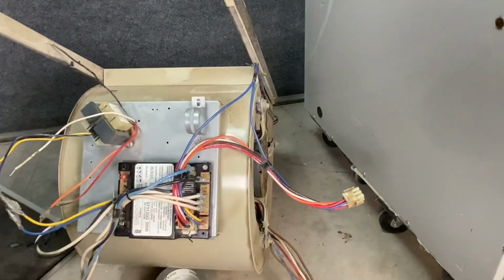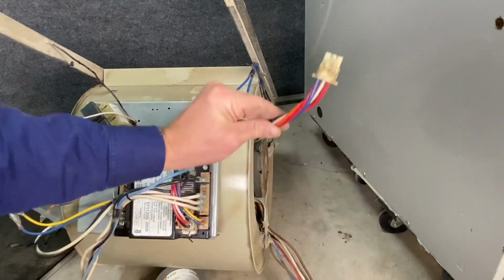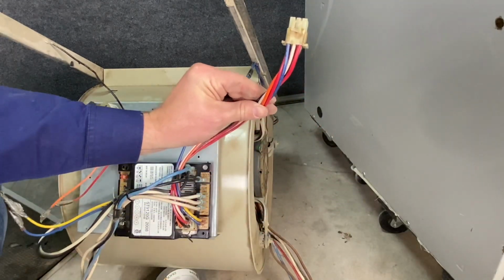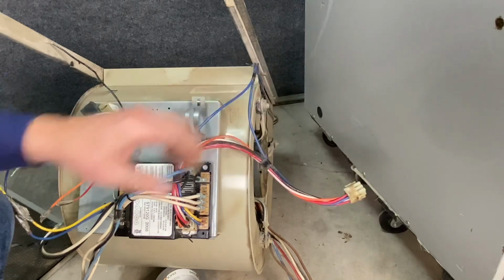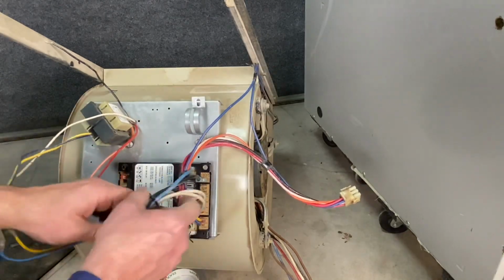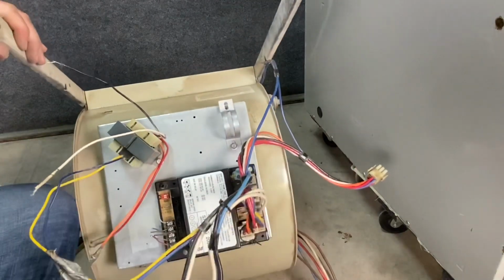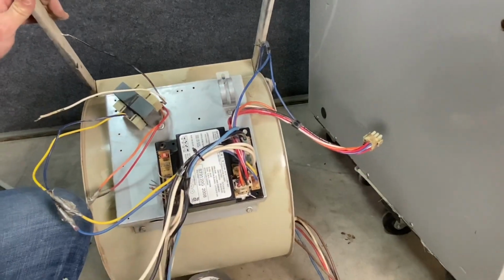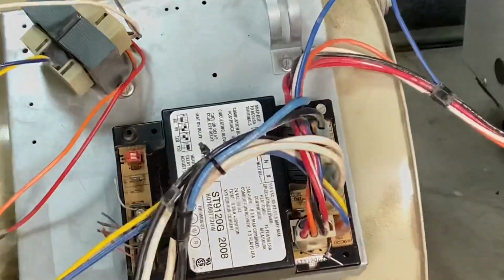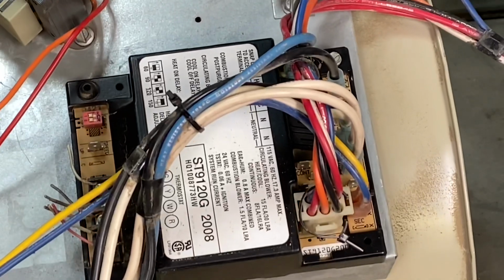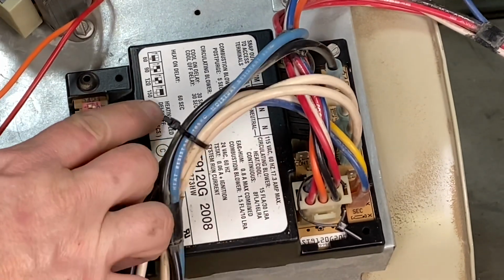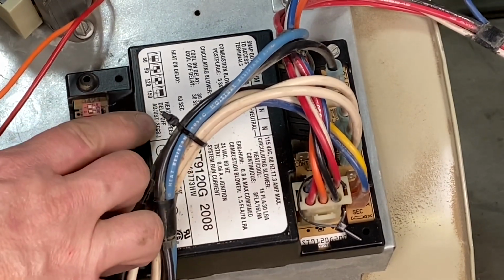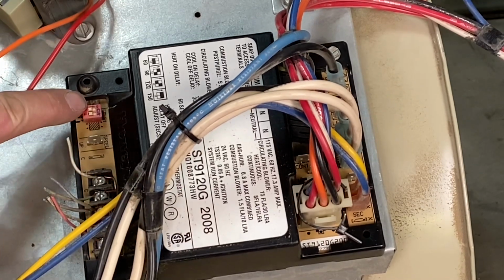The wires that are left over go to all the controls. This plug goes up to the top side of the cabinet for a limit switch, our combination gas valve or smart valve, and all these other components are just for our control board. And I want to show you a few more things in this control board. Here we have, it says fan speed delay off adjustment. So these are our dip switches.